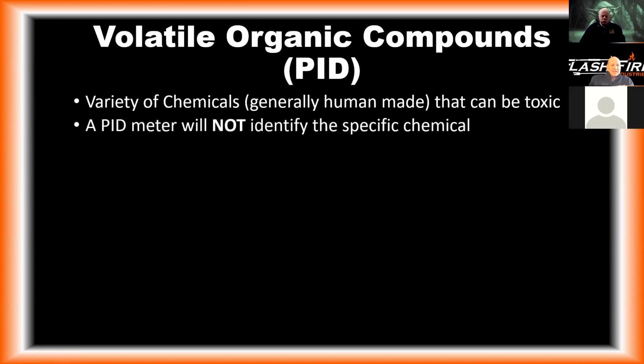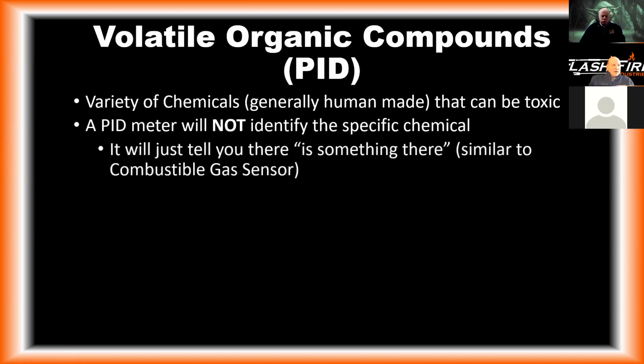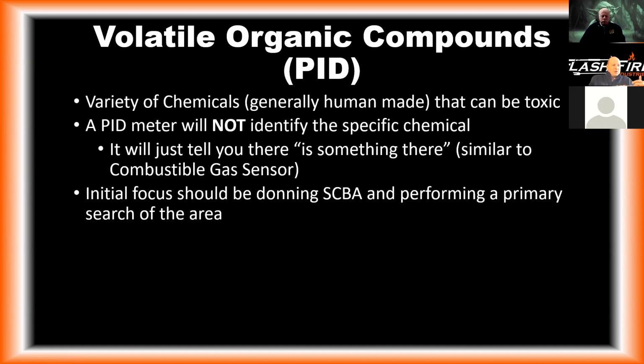It's not going to identify the specific chemical that you're metering, okay? So if you have a variety of different chemicals, this isn't going to tell you, oh, we're reading this one and not that one. Now, you can sometimes use it to narrow down which one you're reading, but by itself, it's not going to identify those chemicals. It's just going to tell you there's something there, as long as it has that ionization potential less than 10.6.